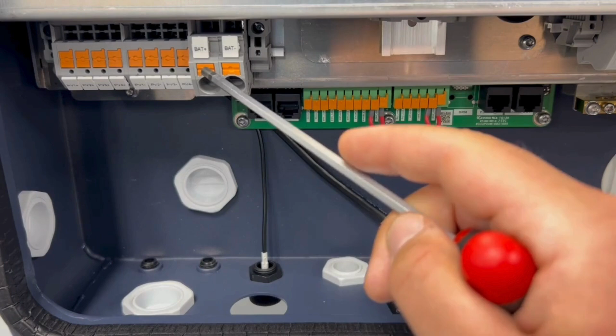First, let's connect the battery plus and battery minus. To do that, first we need to remove this white plastic piece here. This is where the conduit would go, but again, since this is a demo unit, there is no conduit. So now we are ready to put the cable through. The way the mechanism works is that you have the battery plus and battery minus here, and these orange buttons for each.